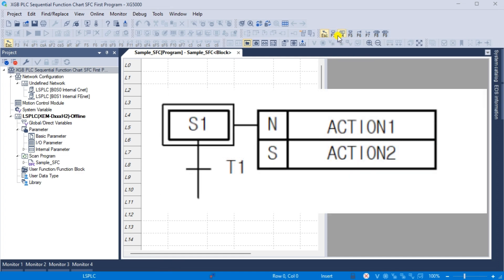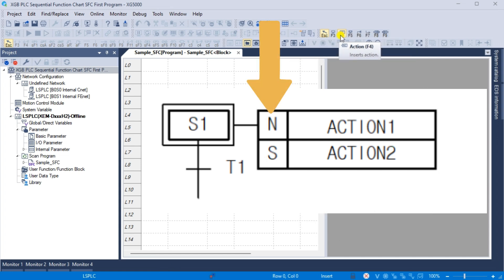Action F4: each step can contain up to two actions. A step without any action is considered a waiting action, which means it waits until the next transition condition becomes true. An action is defined using PLC languages such as ladder diagram, sequential function chart, or structured text, and the action executes while the step is active. An action qualifier is used to control the action. When the action is deactivated, any output contacts activated during the action will revert to zero.